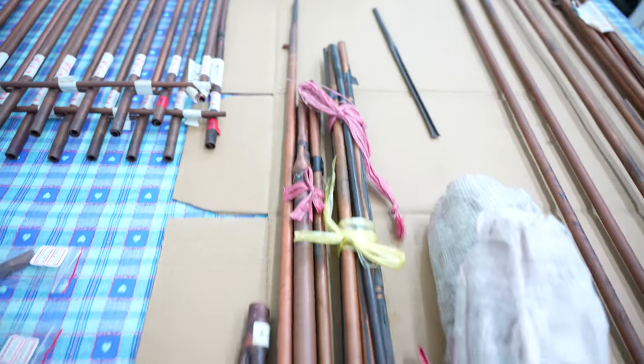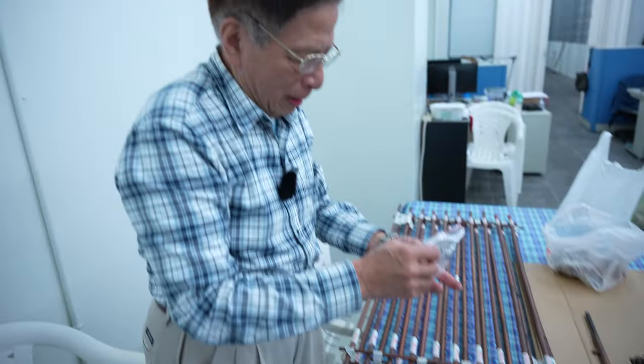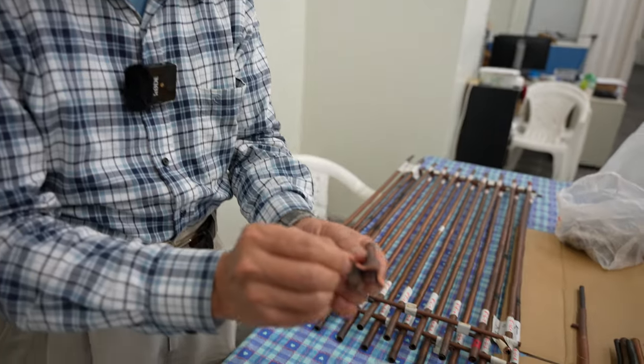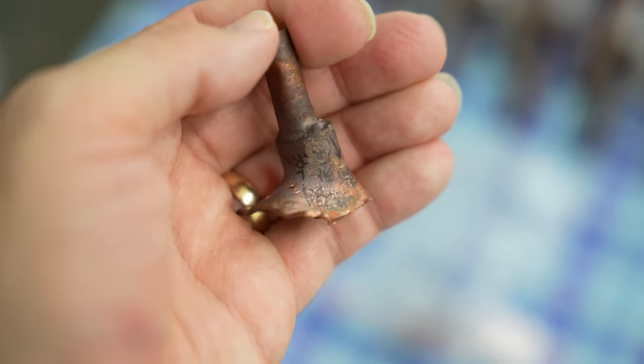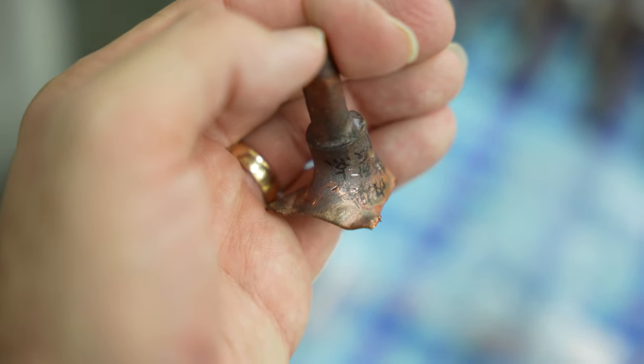This is a material strength problem. And also the pressure is so high it even caused damage in a very strong part of the heat exchanger here — it's very thick. There's a small hole — let me have a look.